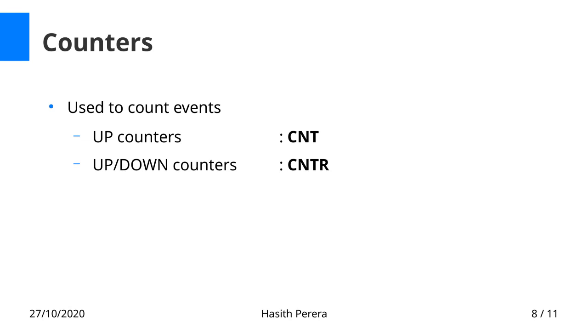So in addition to timers, in Omron PLCs, there are counters. Here we have specifically two types of counters: CNT, which is an up counter, as well as an up-down counter. We have a command called CNTR. Basically these two commands we can use in order to implement counters. Let's say you want to count some number of packages passing. For a situation like that, we can use these counters. We can count the number of inputs we are getting, or things like that we can try out.